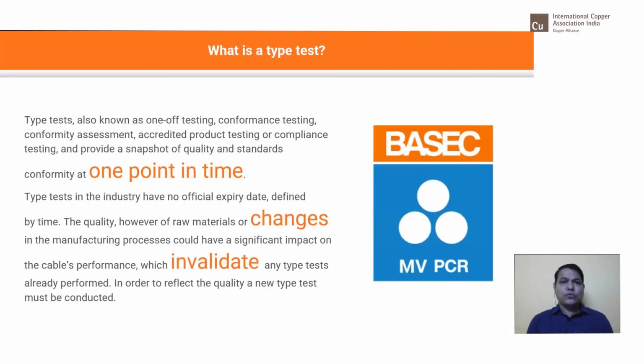So now we are going to talk about what a type test is. Type testing provides a snapshot of the quality of the cable at a certain point in time. It is also known as one-off testing and checks that a cable sample meets the requirements of the relevant standard, to provide a specifier or end user with the knowledge that the sample supplied is compliant to a particular standard. It is useful if a batch of cable is being supplied for a particular project.